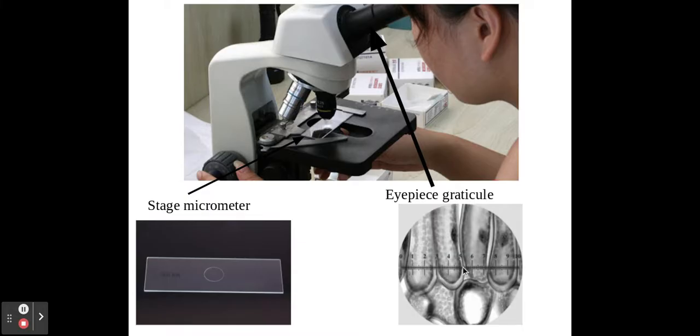We also need to use, once we've counted how many eyepiece lines my specimen is, we also need to use a stage micrometer. So we take the specimen off, we put the stage micrometer on, and this allows us to calibrate the eyepiece graticule so that we know exactly how much each one of these little pieces on my eyepiece graticule actually is.